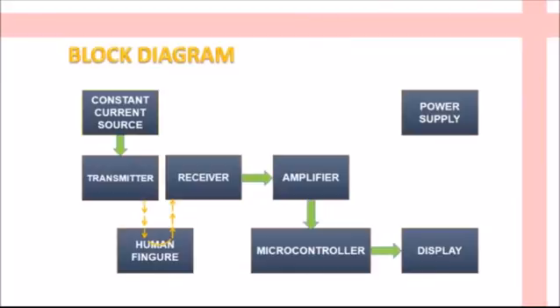Now we look at the block-level construction of the system. The block diagram consists of a constant current source which provides a constant current to the transmitter. The transmitter is a near-infrared LED which provides a constant intensity signal. The reflected rays are received at the receiver, whose signal intensity is very low. A signal conditioning circuit — an amplifier — makes the signal compatible with the microcontroller, which is the main processing unit. A display unit is used to present the final reading.